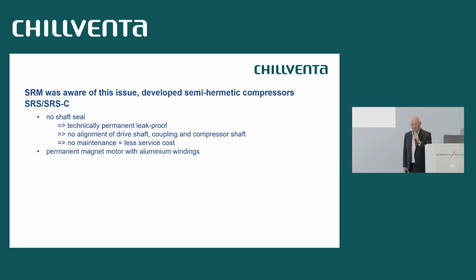The problem with the copper and the ammonia we overcome by using permanent magnet motors with aluminum windings. Of course, you could also use copper windings and insulate them. But if you use aluminum, you avoid the problem of an insulation which is getting somehow cut. Of course, copper has a higher efficiency than aluminum. So if you just use aluminum, you end up with a very big motor, which nobody wants to have.